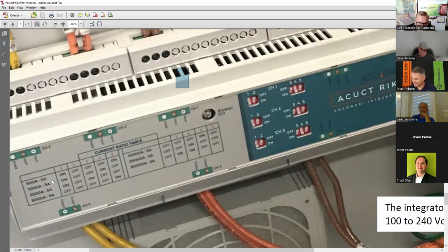So now here is the code, the dip switches. If you have 500 amps as your running current, the maximum peak current you think is going to come into your switchgear is 500 amps, you're going to set the dip switches on, off, off, off, and on. So on, and everything else is off. Here, on and on, the first and the last one, everything else is off.